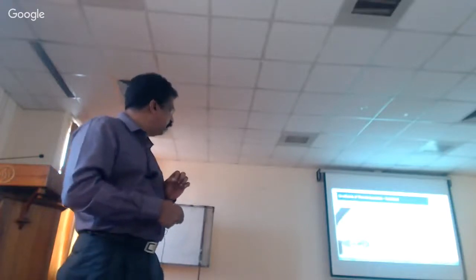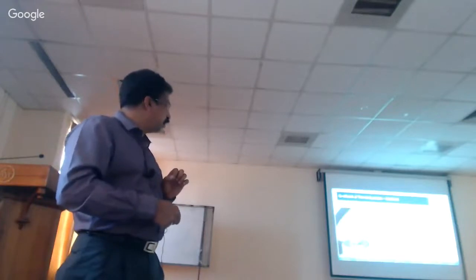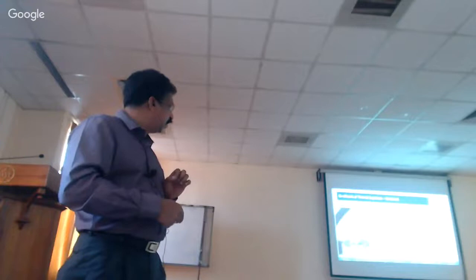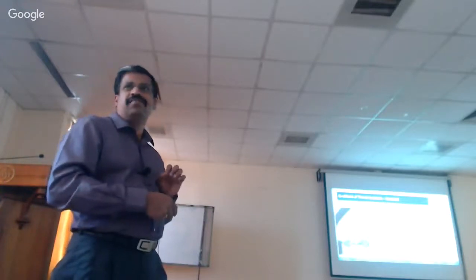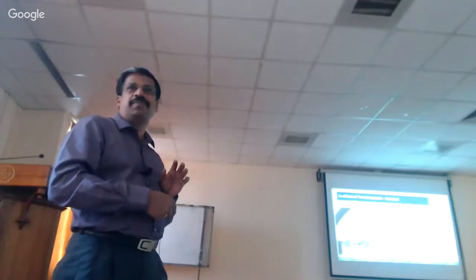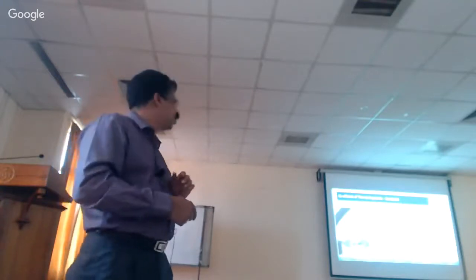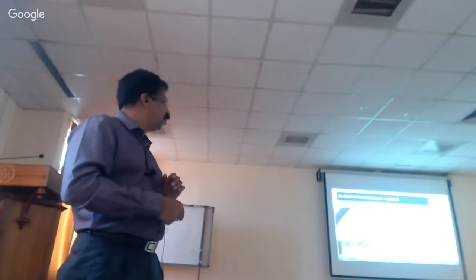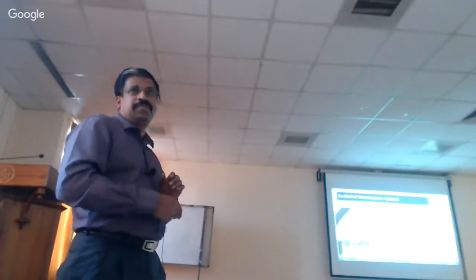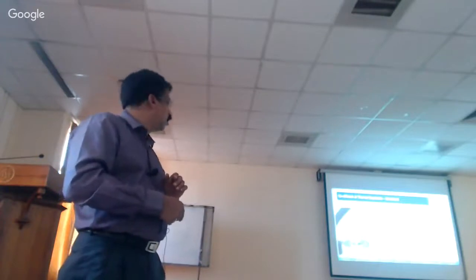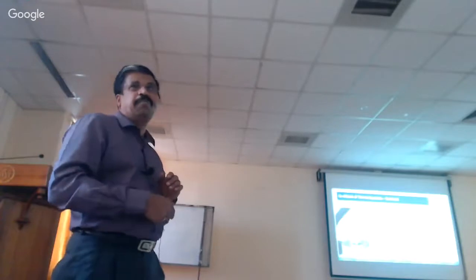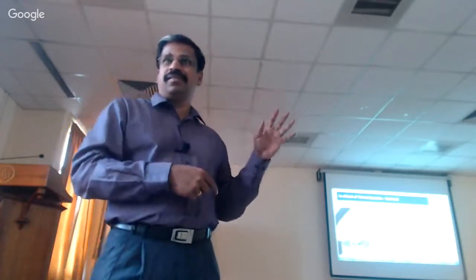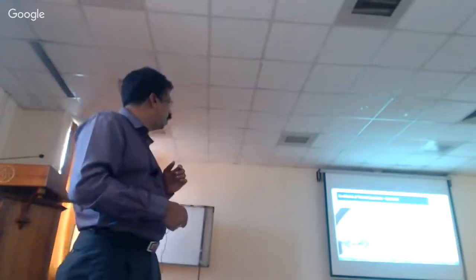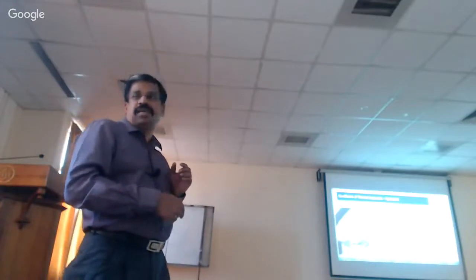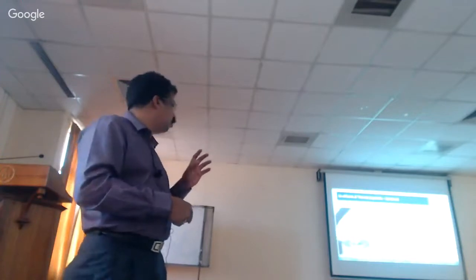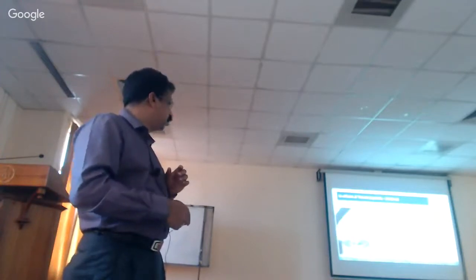And the principle by which it works: there is a sample, a probe which is connected, and an inductive transducer. This is an LVDT. What is LVDT? Linear variable differential transducer, or transformer. When the probe moves up and down, it measures the change in dimension. The changes in dimension are in micrometers, that is 10 raised to -6, while the sample is in millimeters, so it has to measure almost 1,000 times smaller changes. That is why this transducer is used.